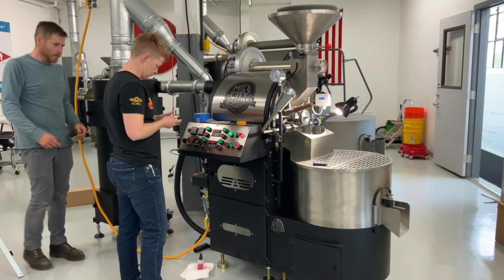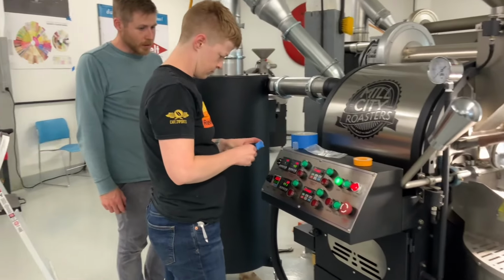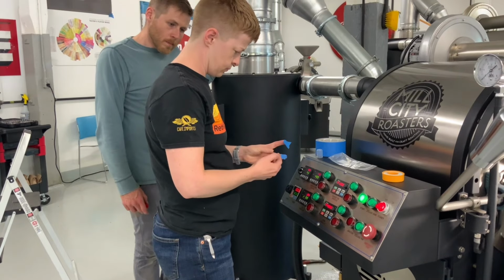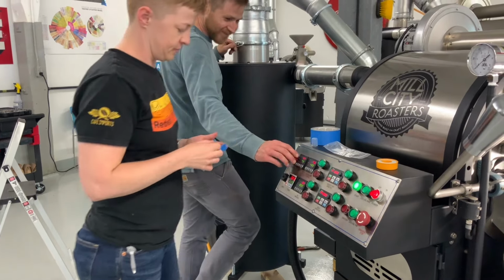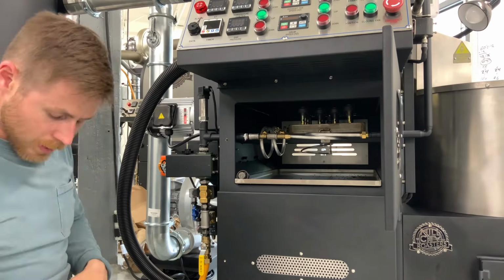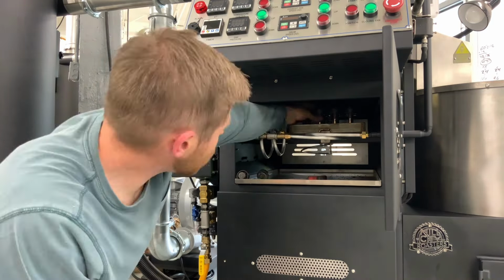Here's an important step. The alarm on the control panel is super loud. We make it a little less ear-shattering by unscrewing the clear red cover and placing a tiny piece of tape over the hole on the buzzer. The buzzer is at the center, surrounded by LED lights. It's black plastic, about the size of a pencil eraser. The goal is just to cover the hole. It's still loud, but it doesn't make you jump.